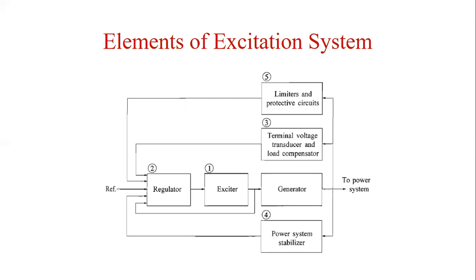First, the exciter: it provides DC power to the synchronous machine field winding, constituting the power stage of the excitation system. Second, the regulator: it processes and amplifies the input control signal to a level and form appropriate for control of the exciter. This includes both regulating and excitation system stabilizing functions, that is rate feedback or lead-lag compensation.